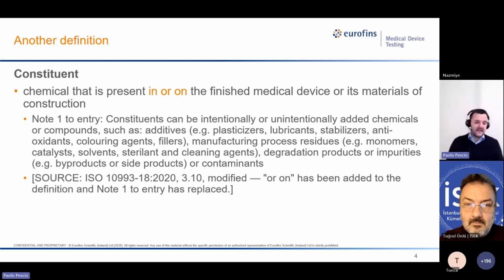A patient, let me say, doesn't care if he or she is exposed to a constituent in the medical device or on the medical device. The patient is interested in the dose he is exposed. And in our assessment, in our chemical characterization, we should take into account the constituents that are in or on the medical device. And to be honest, when we extract the device in order to perform, for example, an extractable study during the chemical characterization, we extract everything that is inside the device and everything that is on the device, on the surface.